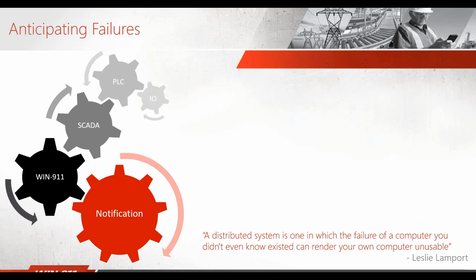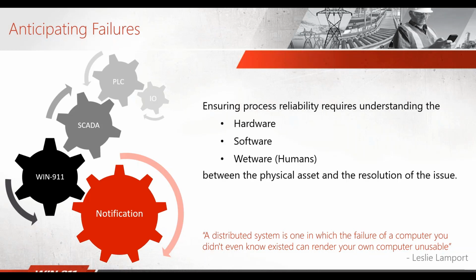First, anticipating failures. We're going to focus our attention today on notification reliability, but we must be cognizant that there are many cogs in the machine. Many things could prevent notification from ever being dispatched, from being received, from being acted upon, or from that action making its way as far back as the SCADA. So let's consider some examples. Hardware: you've got to make sure that your PLC is up and running and connected to the network. Your software could crash. Your SCADA system could go down, and Win911 can't communicate with your SCADA if it's not running. Humans themselves, the operators: are they available? Are their devices available? Have they crashed, or have they gone down or been lost?